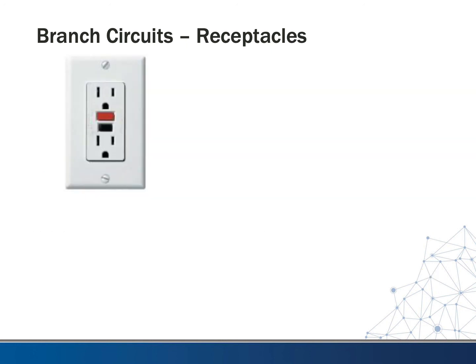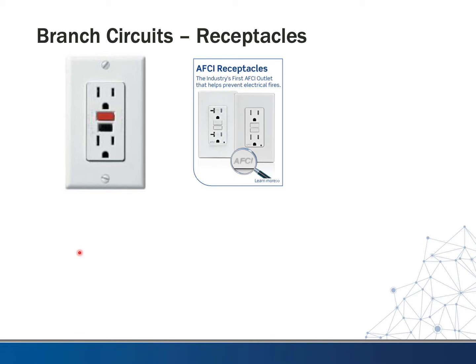Let's look at what these look like so you can recognize them in the field. A common ground fault outlet will usually have a test switch and a reset switch, so you can test the ground fault to make sure it's working. We also have arc fault outlets — where we have arc fault breakers, you can also do arc fault monitoring right at the receptacle. They look like a GFI outlet but will have AFCI stamped on them, usually in the bottom corner.